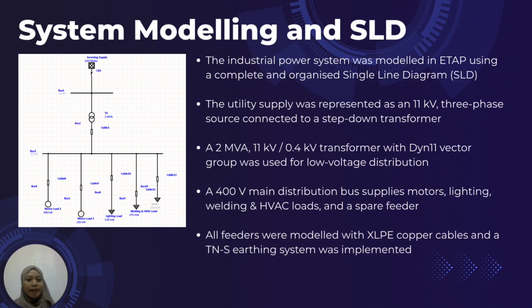For system modeling, an industrial power system was developed in ETAP using a complete and well-organized single-line diagram. The utility supply was modeled as an 11 kV three-phase source, which is stepped down using a 2 MVA transformer to supply the low-voltage distribution system. The transformer is configured with a DYN11 vector group, which allows a neutral point on the low voltage side and is suitable for industrial applications.